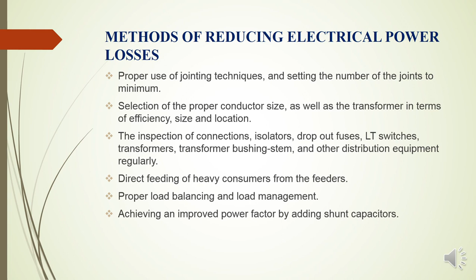The last method we looked at is achieving an improved power factor by adding shunt capacitors. When shunt capacitors are integrated into the distribution network, they introduce a very high power factor correction. In this method, they inject reactive power into the network. This reactive power tends to compensate the reactive components in the network.